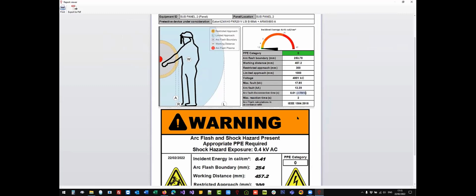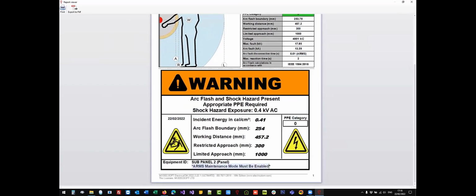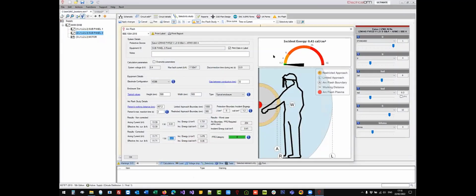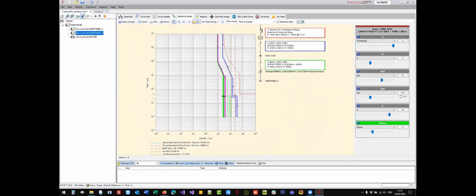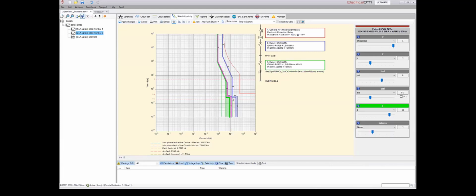So during this study, the designer has enabled the ARMS option. And of course, in the label, we are putting that if you're going to do maintenance, these figures here will be considered when you have the ARMS maintenance mode enabled. Okay, so it's very, very important. Okay, so the ARMS is enabled only when performing arc flash. And when you disable this option for the arc flash, you see it will go back to the selectivity position, the actual position when you're dealing with your selectivity and discrimination and cable sizing.